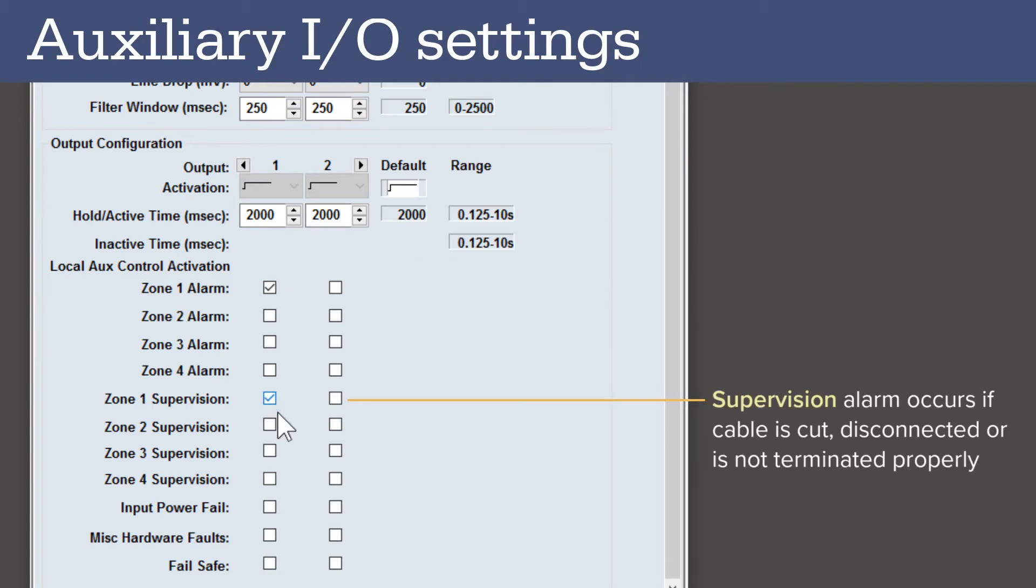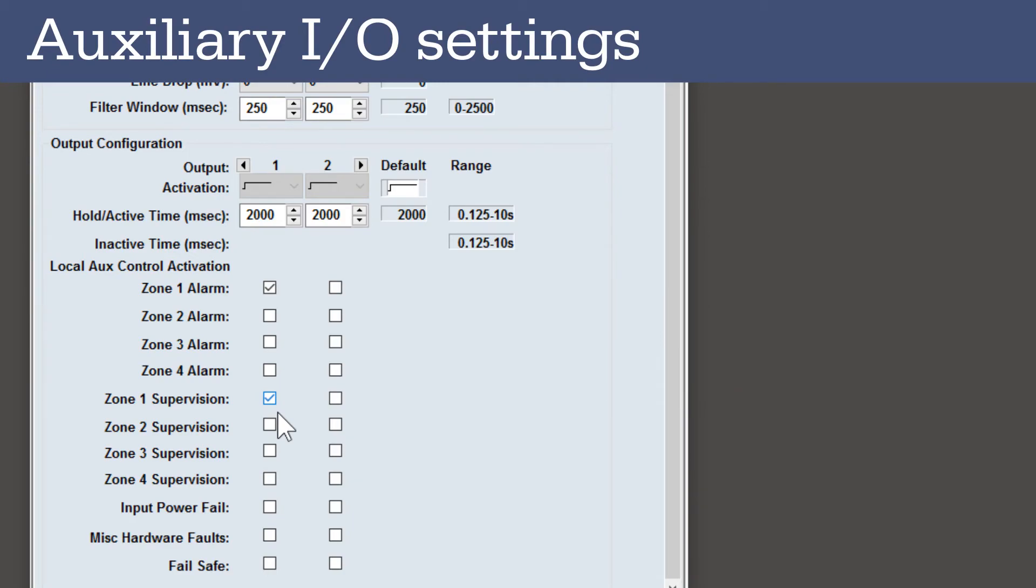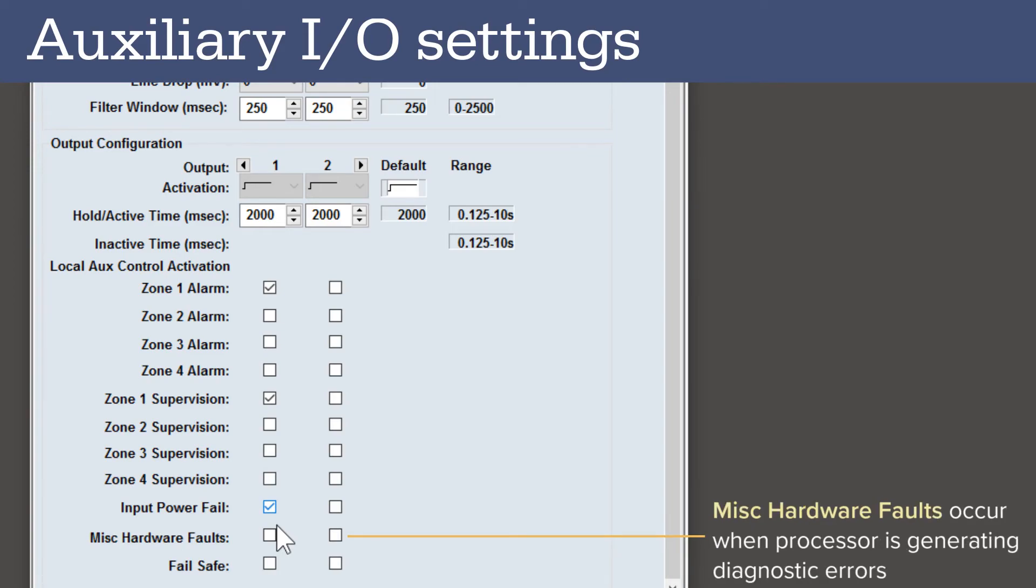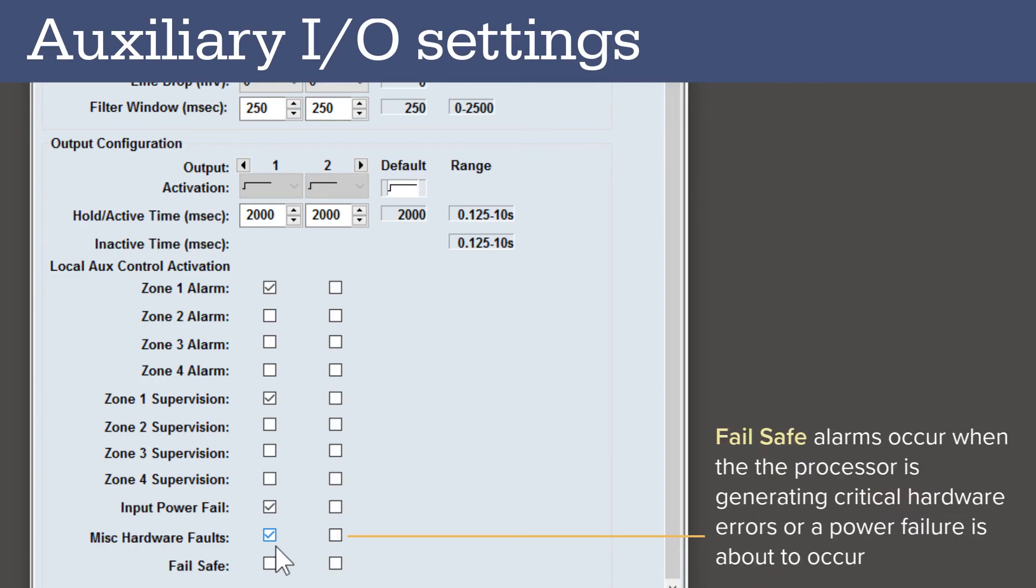A supervision alarm occurs whenever the sensor cable is cut, is disconnected from the processor, or is not terminated correctly. An input power fail occurs when the processor's voltage level is outside the required range. Miscellaneous hardware faults occur when the processor is generating diagnostic errors. Fail-safe alarms occur when the processor is generating critical hardware errors or a power failure is about to occur.